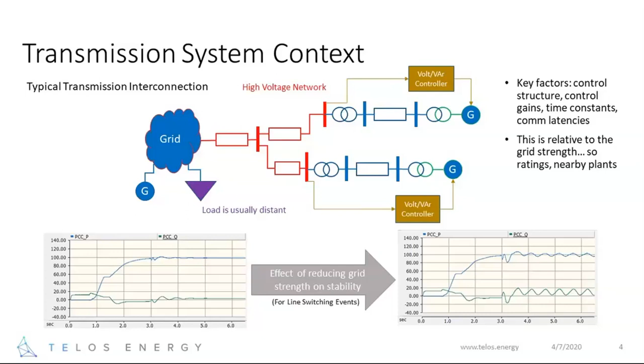So in this case, there are two generating systems, aggregate, right, each composed of many modules of some inverter-based resource. There is a Volt-Var controller that is local, that is measuring some voltage node, usually at the high voltage point of interconnect, and providing direction to the inverters, which are then injecting VARs to modify that voltage. And this can happen in many places, and then it's all grid interconnected, and typically the load is distant, so you're transferring the power over some long distance lines to the grid.